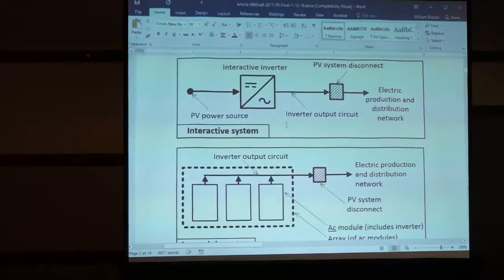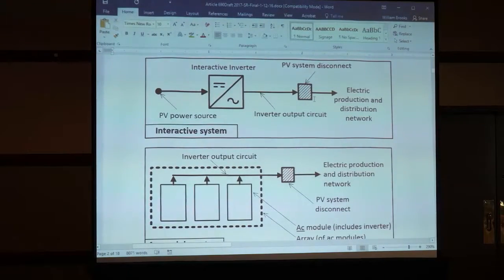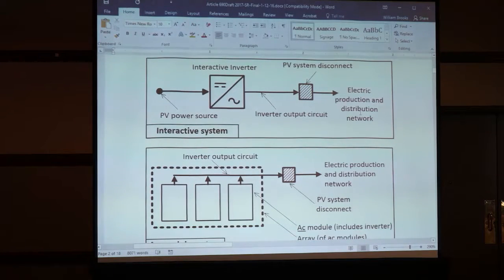Okay, so if I turn off the PV system, I know that that PV system is isolated from the building conductors. There are no load conductors whatsoever in the building attached in any way, shape, or form to that PV system. And if I have a battery, the battery is on the non-array side of that PV system disconnecting means. Okay, so the very simplest system is going to be right up here, and let's make this bigger here. So that's the system that is by the millions going in today. It's the utility interactive inverter. There's your PV system disconnect, and then it goes into the electric production and distribution network, which is a fancy name for whatever's connected to the utility.